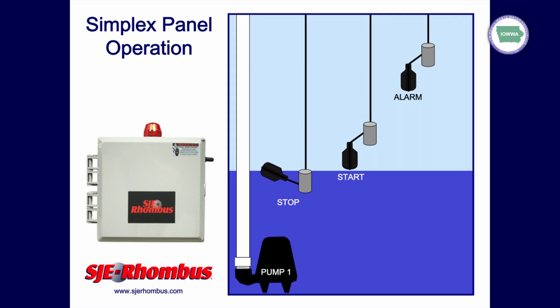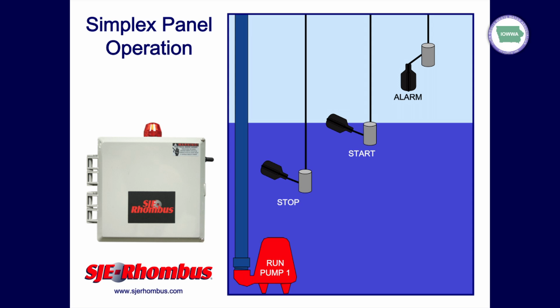And this graphic will just go through what actually happens in the tank. Liquid level comes up. When it hits the stop float and raises the stop float up, nothing's going to happen. Once the start float is reached, it's going to energize a coil inside the control panel, pull in contacts of the motor contactor, send power to the pump, and start your pump running.